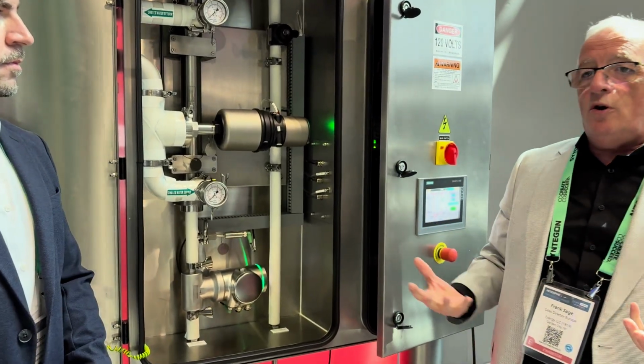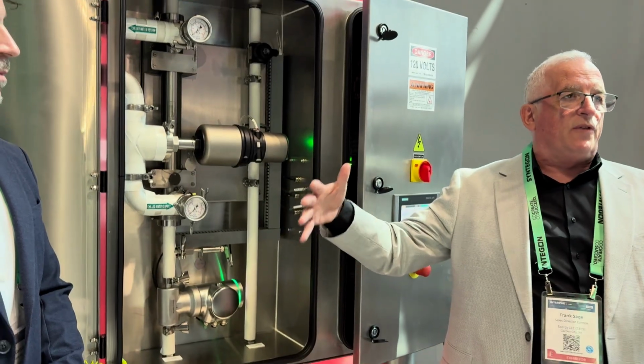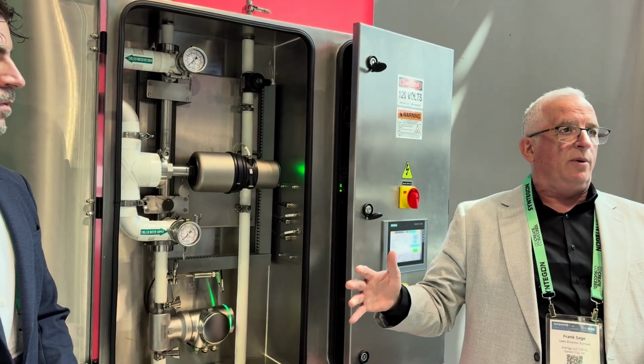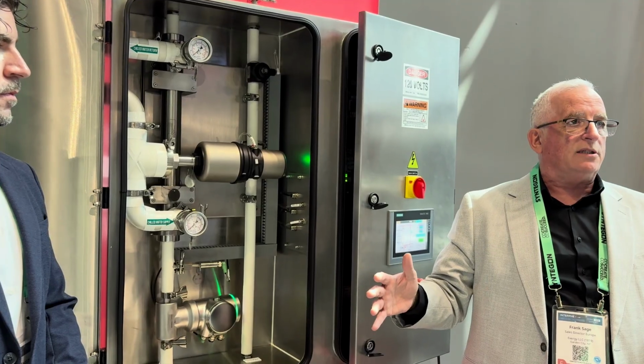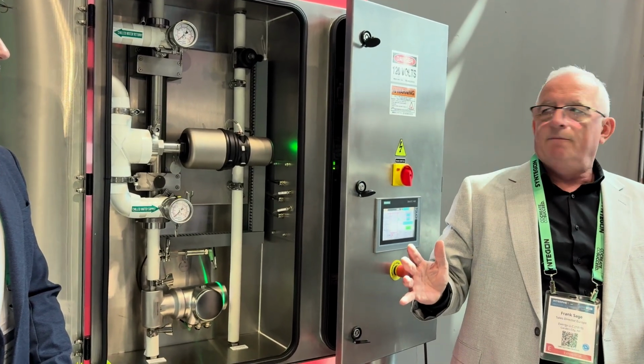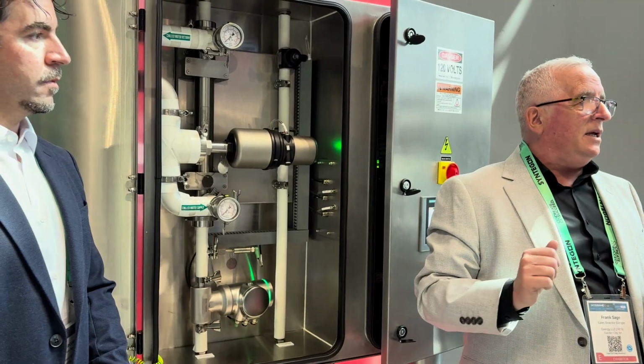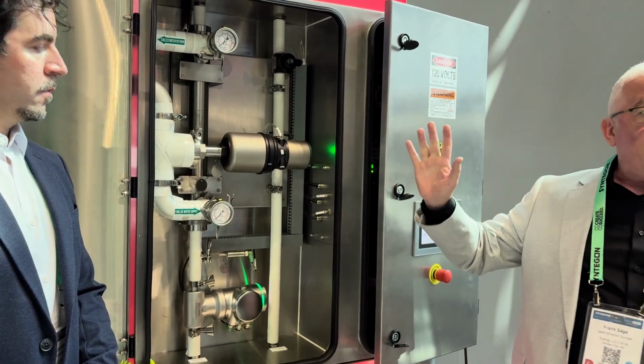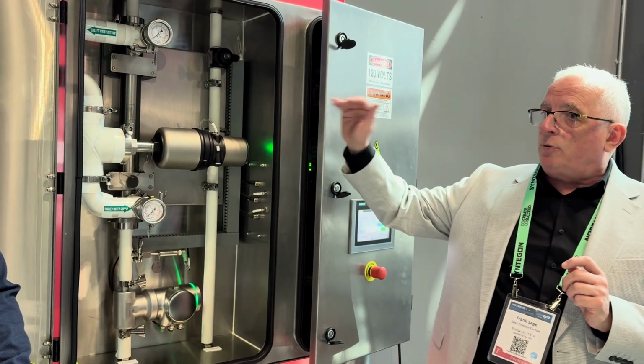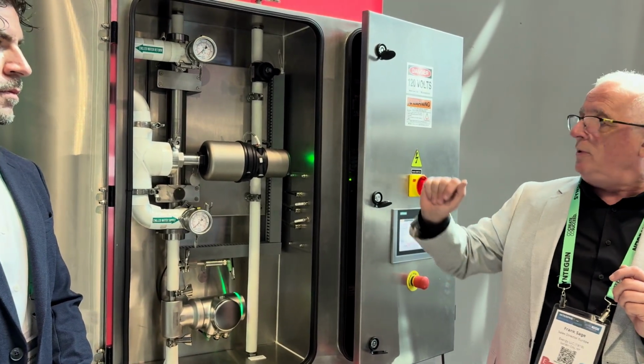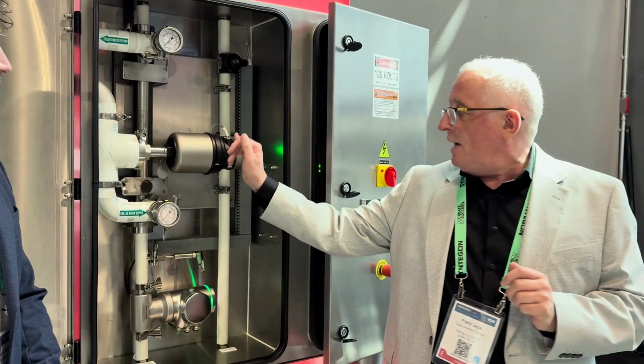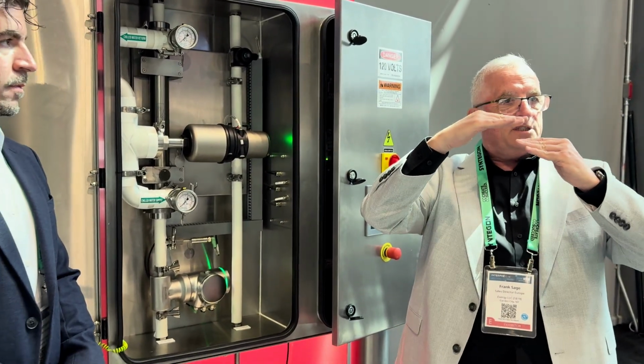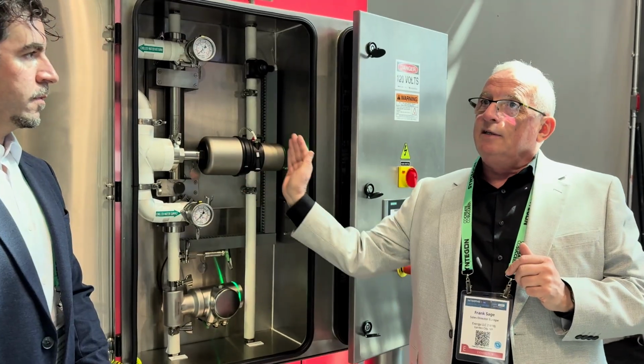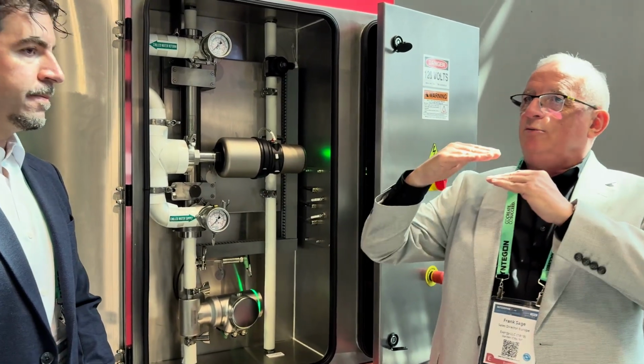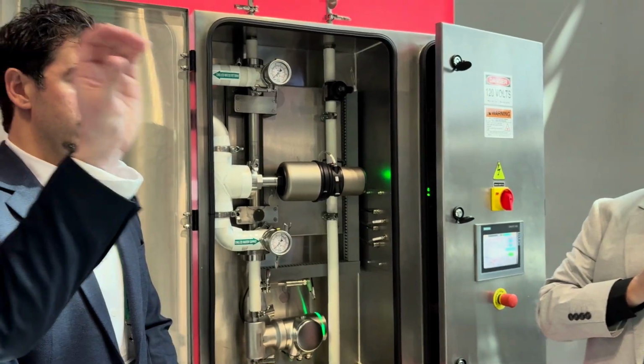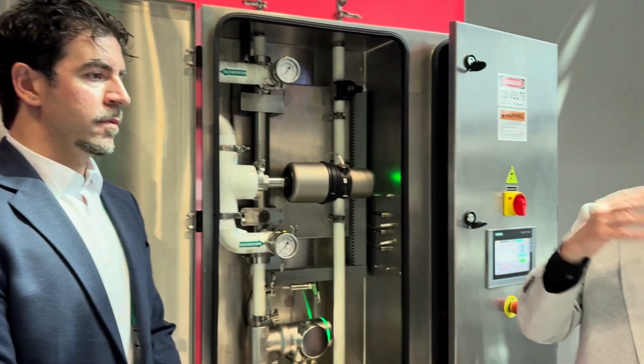A typical chromatography skid will need a significant buffer tank to maintain the flow of WFI during the chromatography process. They can't be starved of WFI. Our customers don't need a buffer tank any longer because we waste no WFI. And at every process step, we actually configure the Burkert PID controller. We program 6 steps so that even the hunting, if you like, is greatly reduced. It's essentially modulating each step. Exactly, as we do that within the factory.